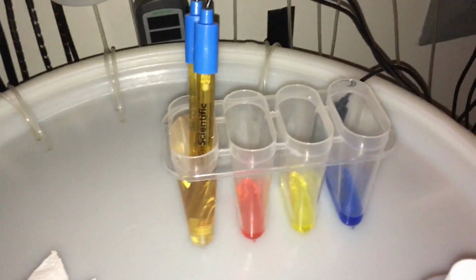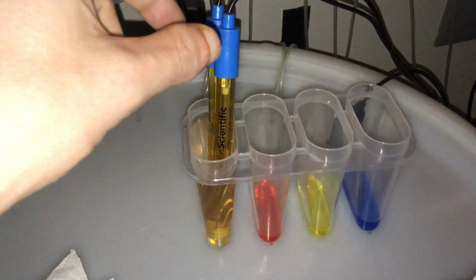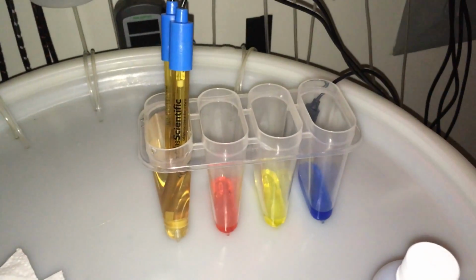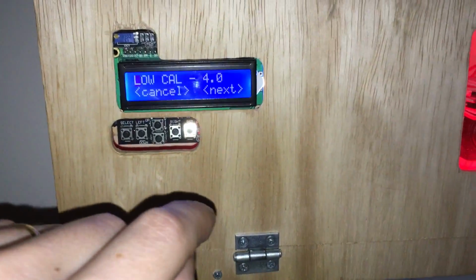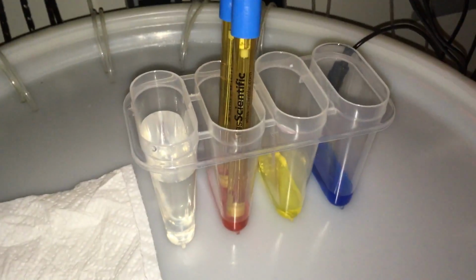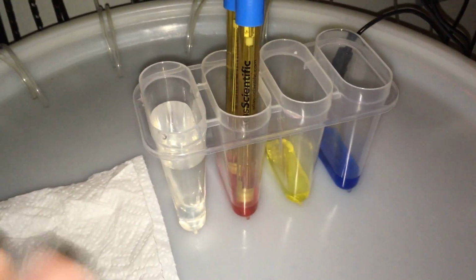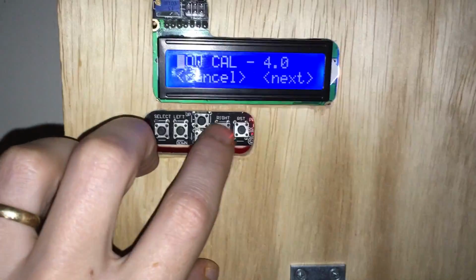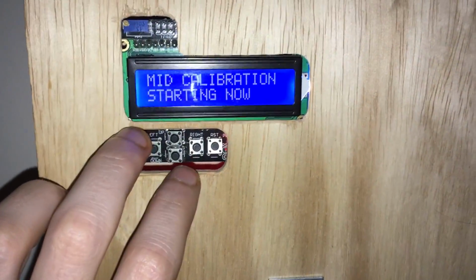and it's going to say low calibration starting now. So what we're going to do is take these out and dry them off and then stick them into our low, which is the 4.0. I'm going to do a little jump cut here because I only got one hand. Okay, I've gone ahead and dried them off, moved them into the 4.0 solution, and on the low calibration, it's anticipating 4.0. So you might want to just let that sit for a little while, maybe 30 seconds, let the probes catch up, and then we can move over to next. Mid calibration starting now. So same deal, we're going to take these probes out, dry them off.